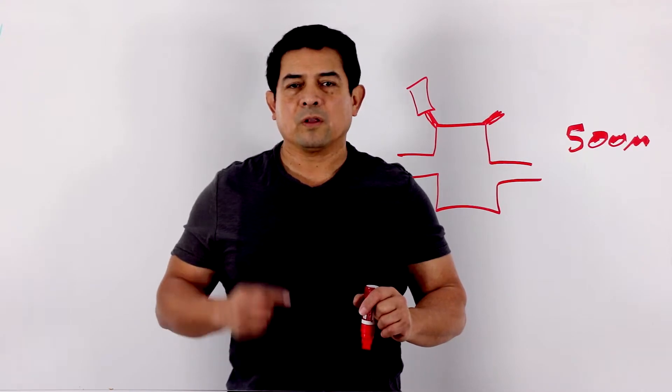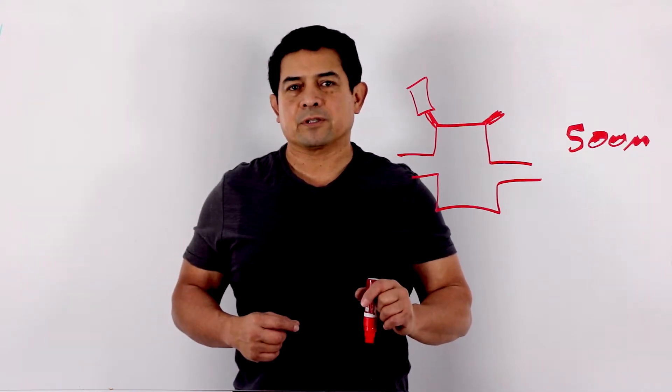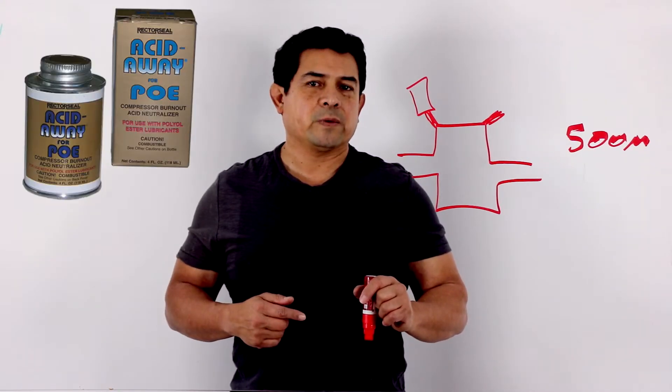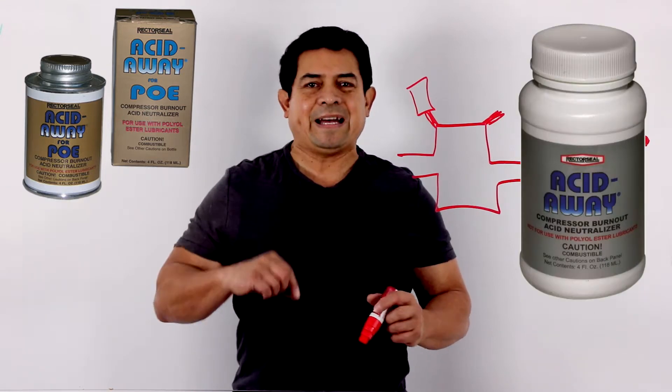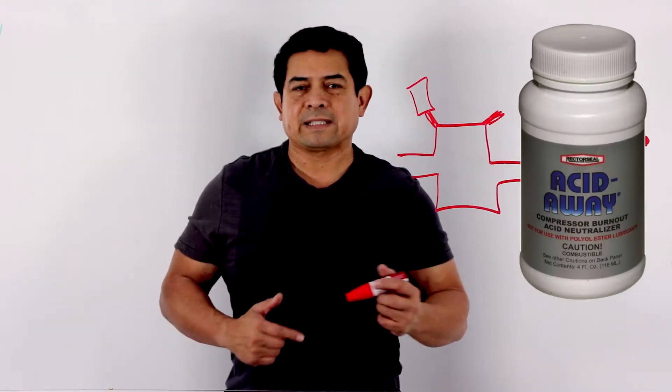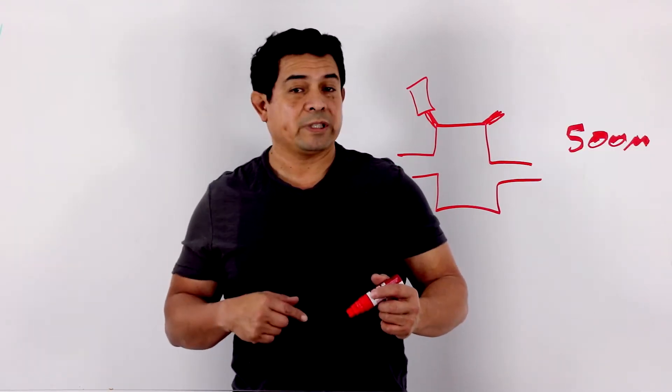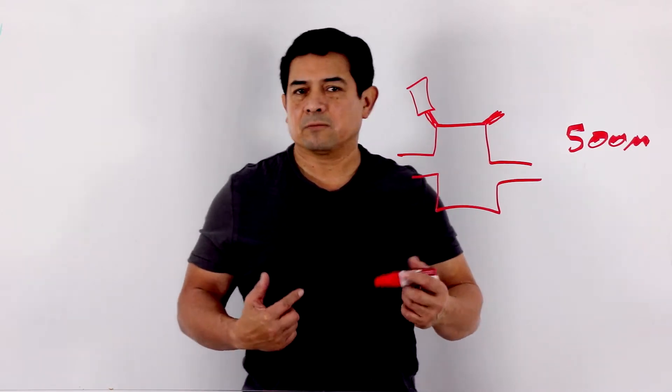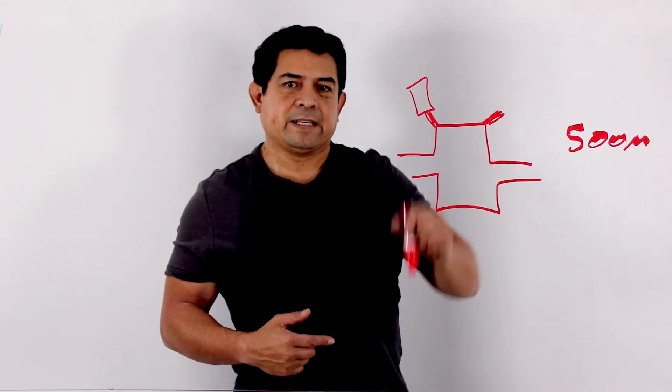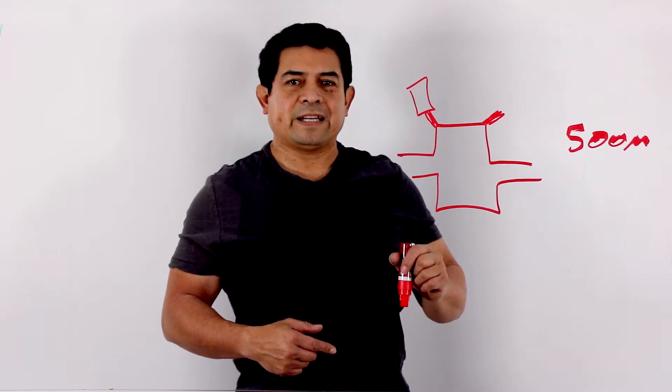What are you going to treat it with? Well, they have these acid scavengers, they have this stuff called Acid Away. They have different things that you can just add onto the system and it neutralizes the acid. Once you put that in there, you come back two, three days later, test it again. See if it still has acid in it.